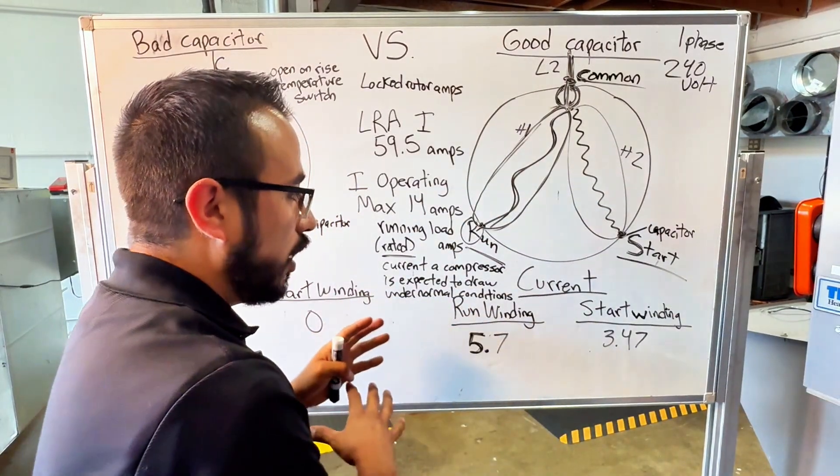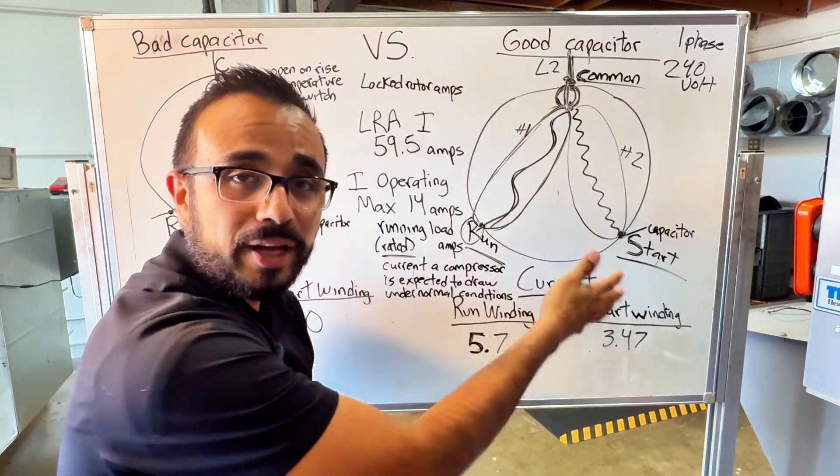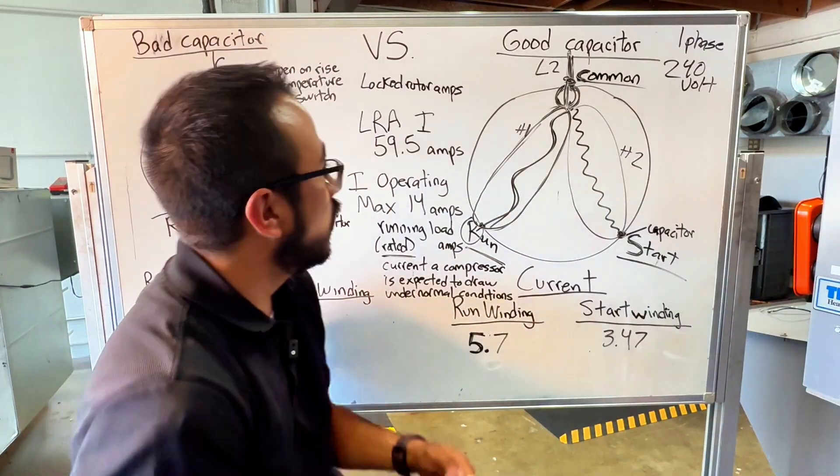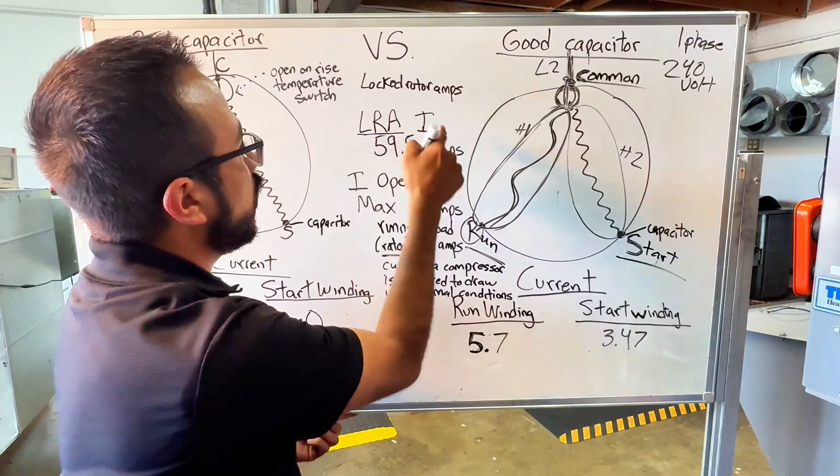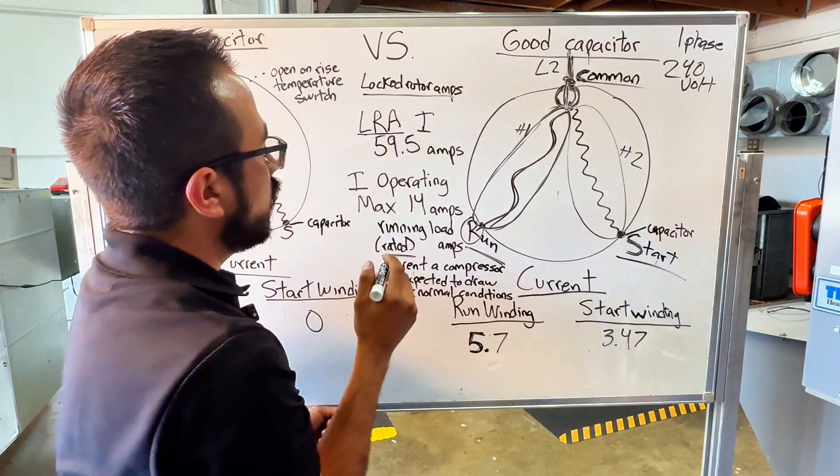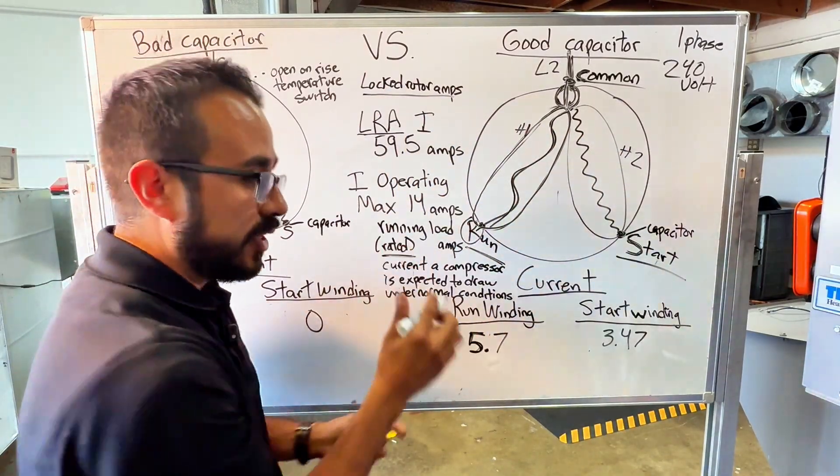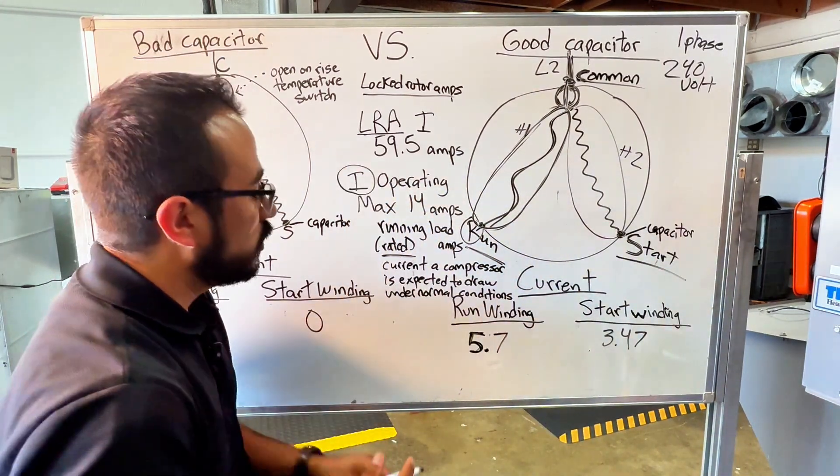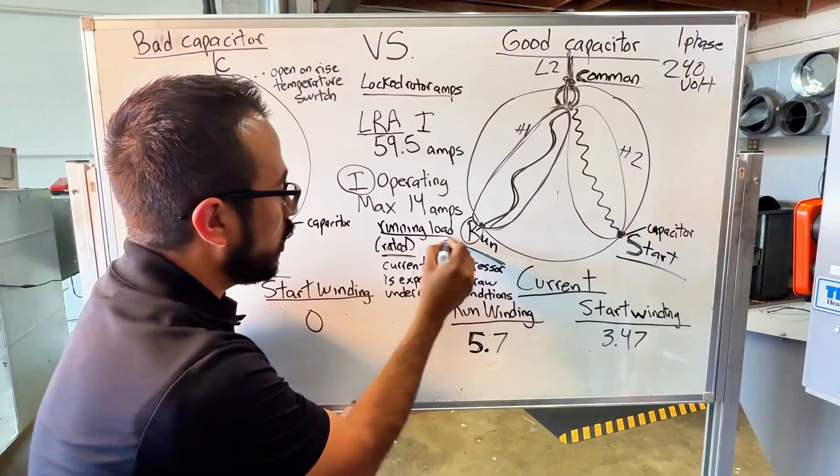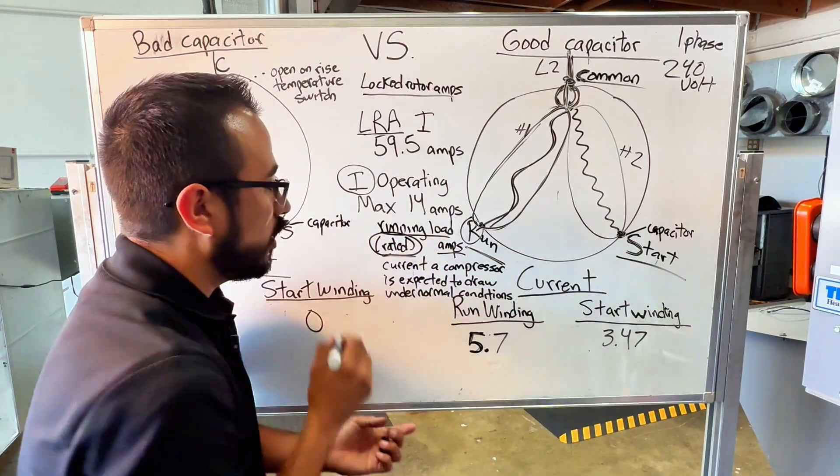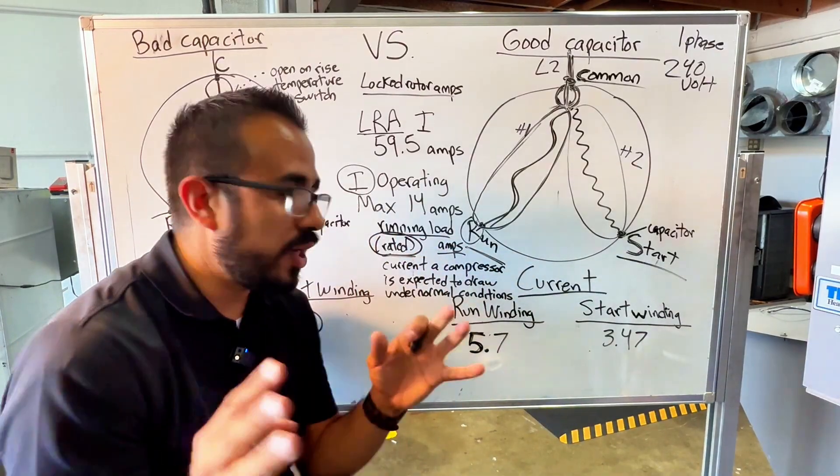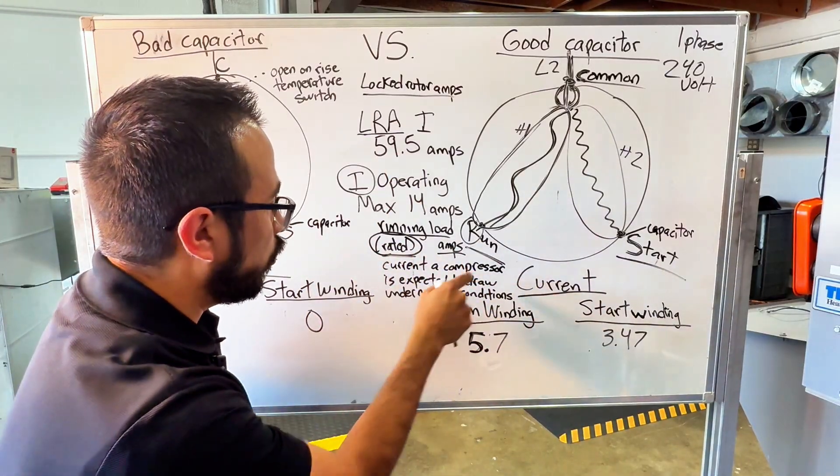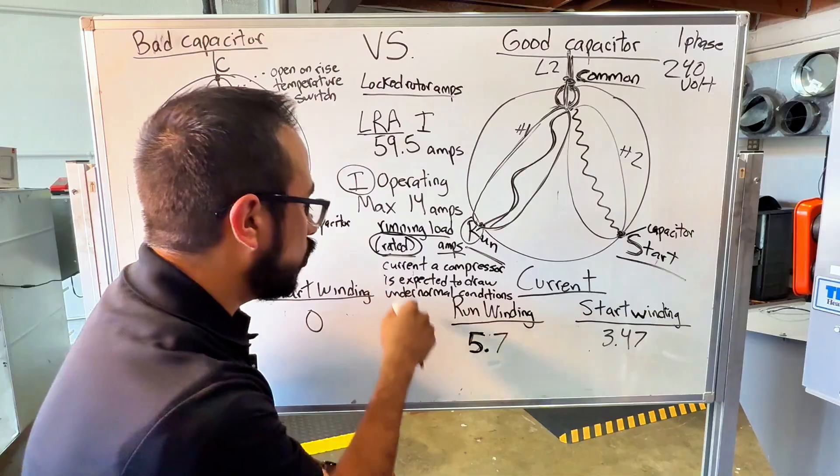So even though there's power going to it, it's stuck on one side, it cannot complete the circuit. And the reason why is because the run capacitor was weak. It didn't turn that compressor over. It didn't have enough current to have to start winding so it can start working and pumping. But I really wanted you to see that number. It was at 50 something, which we're going to write on the board. It was pretty high and boom, one to zero because the thermal overload opened and now it's protecting the compressor from overheating. Okay, so before we compare the current from a good capacitor to a bad capacitor, it's important for you to understand two terms. One is locked rotor amps, LRA, locked rotor amps. And then the other one is operating max. At least in this specific one, they refer to it as operating max current. Sometimes you see it as running load amps.